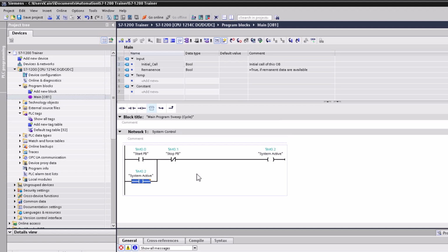So it basically downloaded to the PLC program right now, or to the PLC processor right now. Now, you can't see anything because we're not online with it. So we're going to click go online. And then we still have a couple steps with that as well. When we go online, you see that everything is green, which is a good sign, right? If we had any amber or orange, we would not be in the correct spot. In this state, you see we don't have any activity down here.